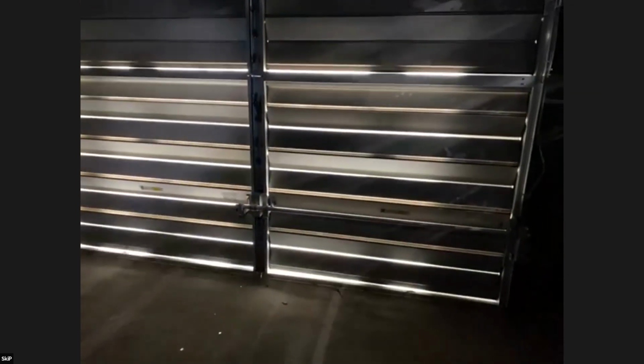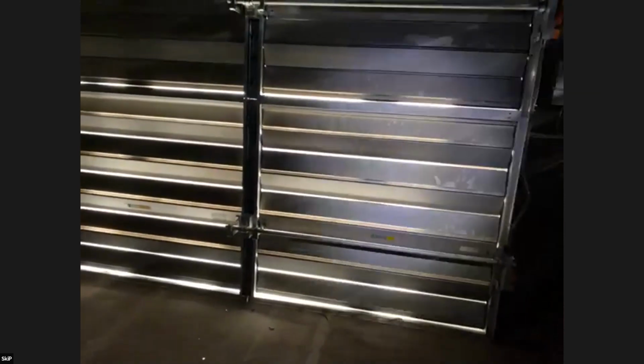And so what that's called is outside air economizers. We're making the thing run more economically by bringing in outside air when it's the correct temperature. When the temperature changes and gets warmer, and I'm trying to keep up with the whole building, then I close off these dampers and I don't bring in as much.